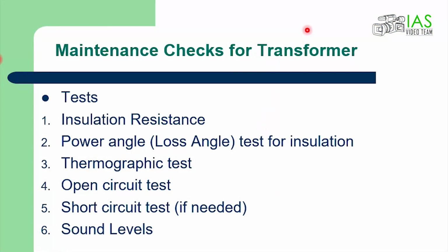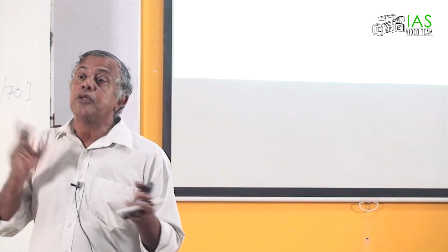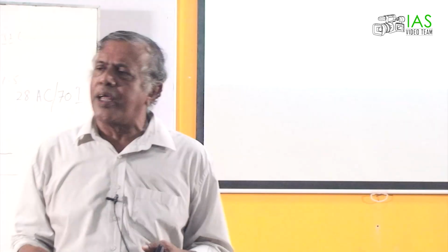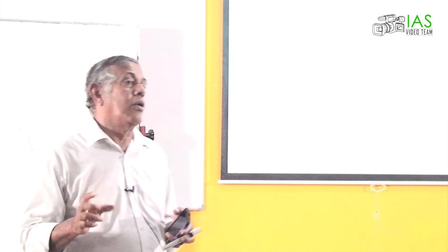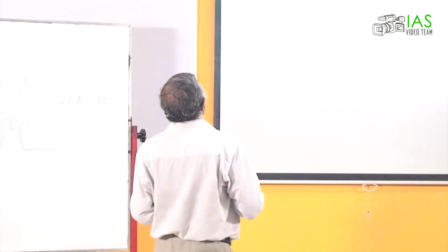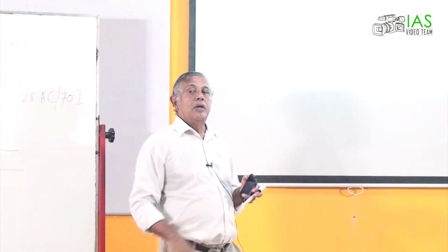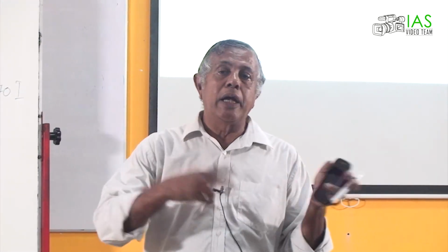So the tests are insulation resistance, power angle, and thermographic test, open circuit test, short circuit test, and sound level. And you have done about these things. The short circuit test definitely you have done, maybe in second year or third year, I don't know. With the short circuit test, you are determining the percentage impedance of the transformer, or it's called voltage impedance also. Now, open circuit test is putting the voltage to one side and checking the ratio.